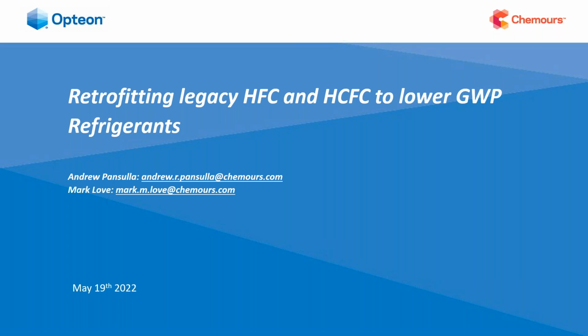No, that's a good question. I'll try to answer this. There's a lot in that to answer, but for 22 refrigeration applications, that was really the focus of where 449A should live. 449A actually is not SNAP listed in air conditioning applications. So right now, if you have a 22 air conditioning unit and you cannot change the oil in it, MO99 would still likely be our recommendation. If you can change the oil in a 22 air conditioning unit, so if it can run on POE oil, then something like 407C would make sense. But the focus of 449A and its applications would be low temp, medium temp refrigeration.